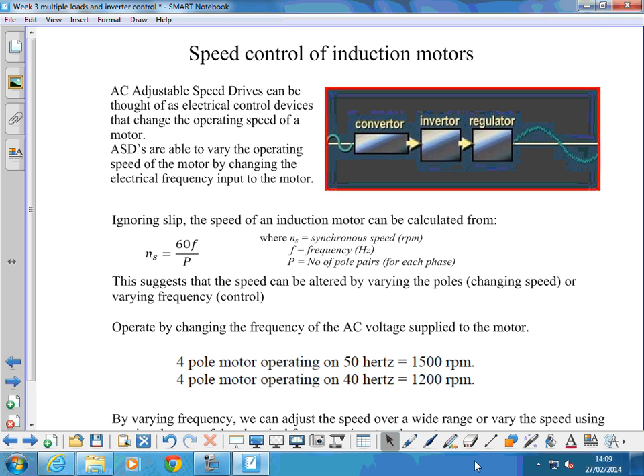Okay, remembering from last week, if we ignore slip, the speed of an induction motor, its synchronous speed, can be calculated from 60 times the frequency over the number of pole pairs on each phase. So that formula suggests that we can alter the speed of the motor by either varying the number of poles or varying the frequency.